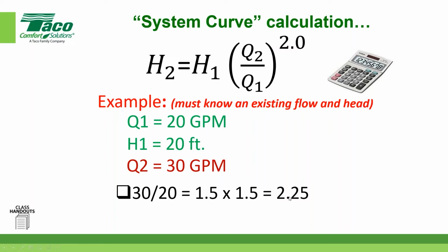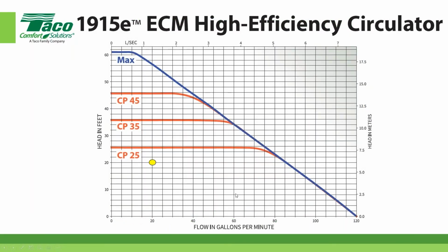1.5 times 1.5 is 2.25. The 2.25 now becomes my multiplier that I use against the old head. So I take the old head at 20 foot times 2.25. If these numbers are good, you'll be dead nuts on at 45 foot of head. So it wasn't intuitive. It goes way to hell up here.